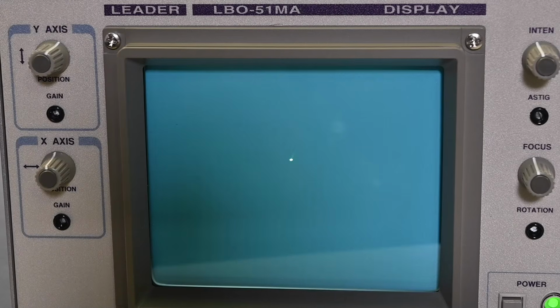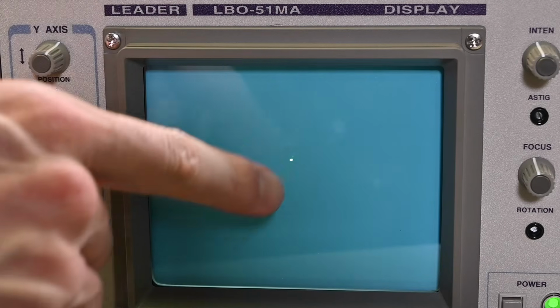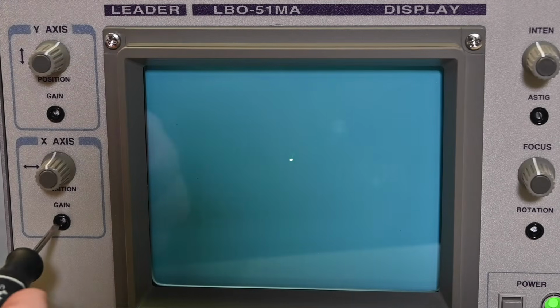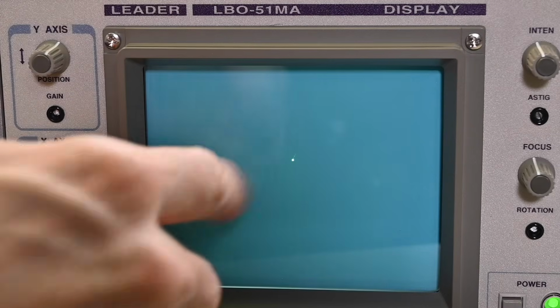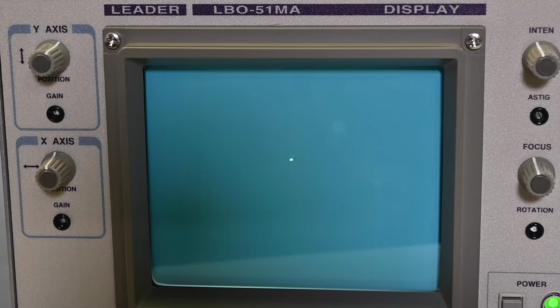Right, so I repositioned the wiring coming off of the transformer terminals on the primary side, just bent them down at a 90-degree angle so it's well away from that BNC connector, and it's much improved. Check it out, it's a very sharp dot, and the gain is at the maximum, but if I turn it all the way from maximum down to minimum, it remains a very sharp dot in the whole range. So that looks like it's working correctly now.